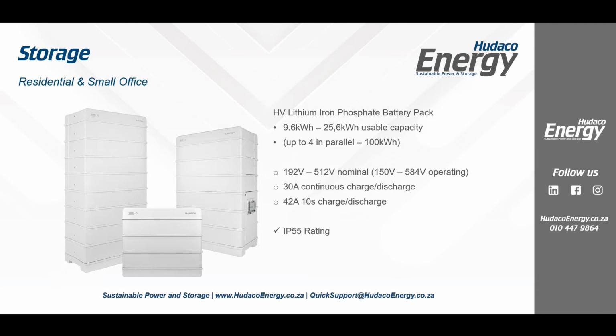What we didn't talk about in the basic training is that we can also parallel up to 4 of those stacks if we need to. So your client could have a 6 kVA, well, let's call it 13 kVA if we take into account the non-load shedding aspects, with up to 80 kilowatt hours on a single inverter. The voltage on these runs up to about 460. The discharging and charging rate is 30 amps.